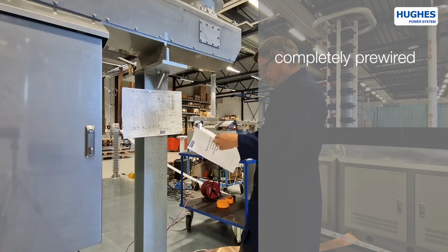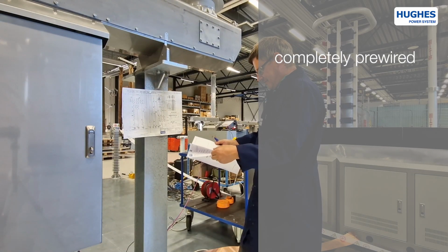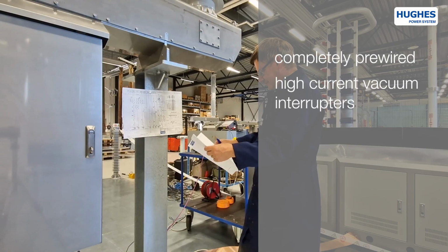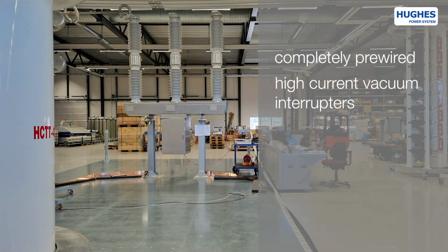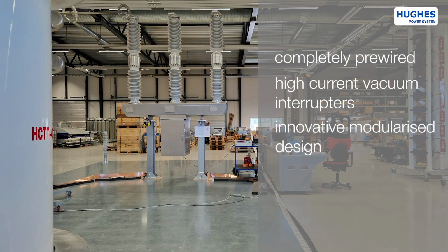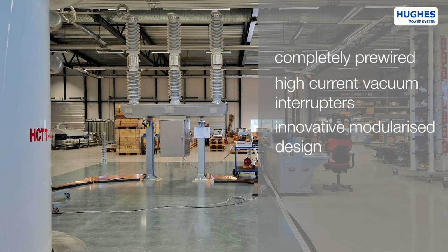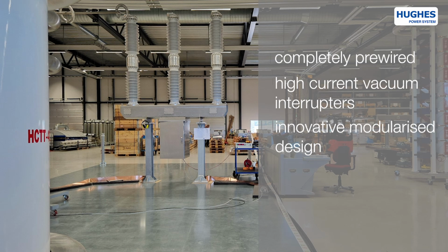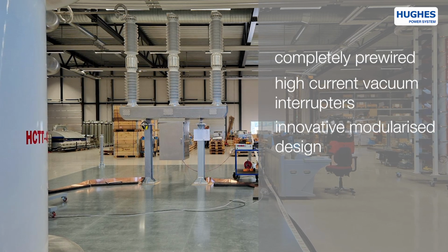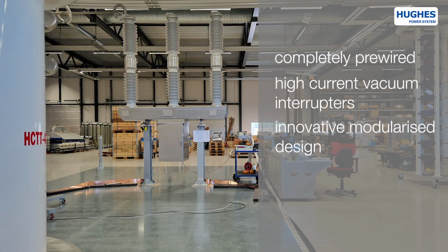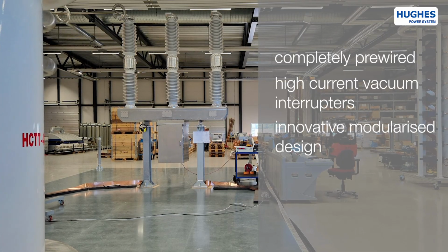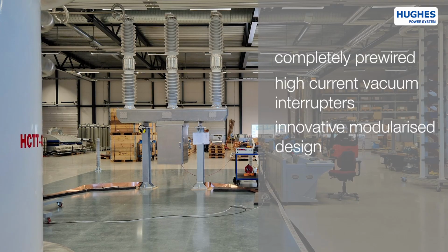The electrical contact has the pre-wired SCADA interface that provides information about the switch position. It also connects to multiple cam switches and the heating element. High current vacuum interrupters do not produce any harmful switching products and are easy to replace in comparison to gas-insulated interrupters. The vacuum interrupter has an innovative design, allowing the unit to be modularized for 1, 2, 3 pole versions for different applications. Normally, 2 pole versions are used for railway electrification and 3 pole versions are used for electrical transmission systems, including renewable energy sectors.